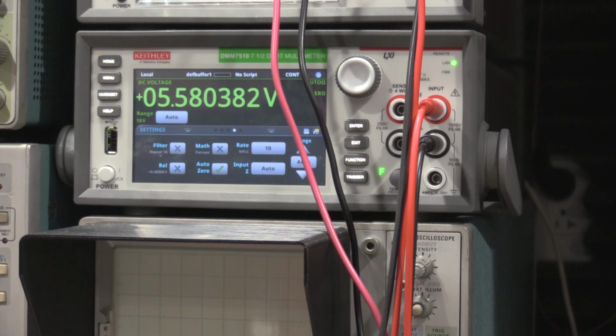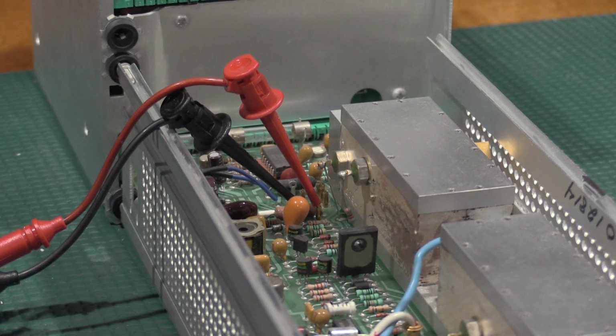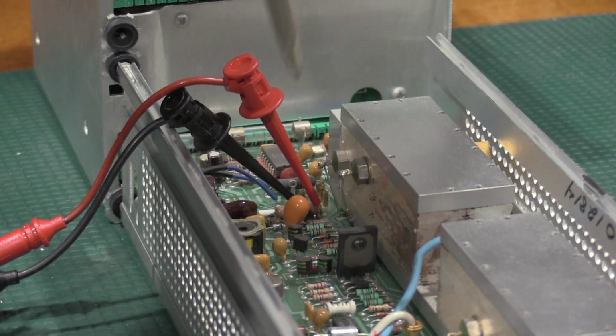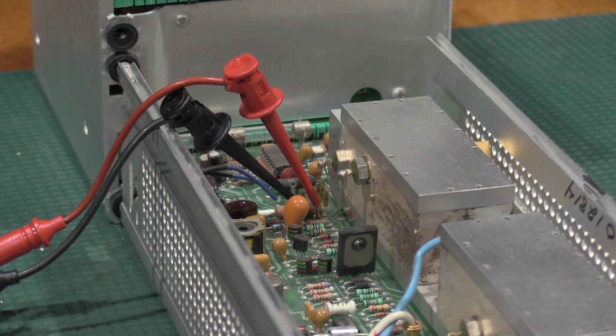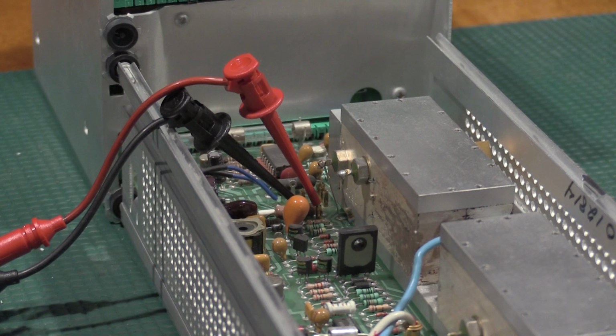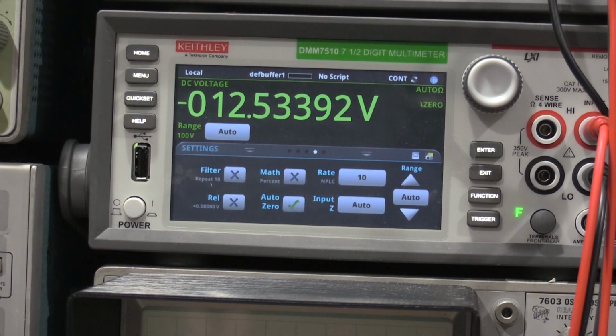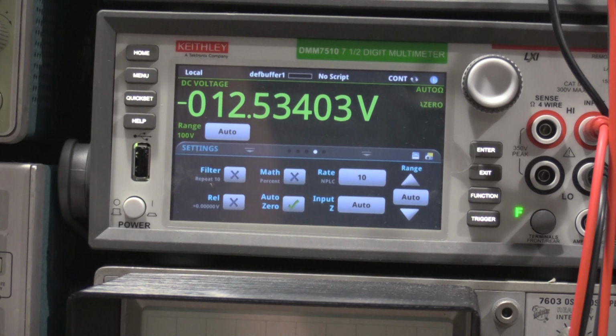Record a value that is 0.4 lower than the actual reading. Record this value, we use it in step 6, part 8. All right, so 5.58 minus 0.4, which would be 5.18. Okay, test E is the test point right up here with the ground, and I'm looking for negative 12 to negative 12.9 volts on the meter. We have negative 12.5, so our buffer bias voltage is perfect and right in the middle. So next we need to check the output of the 0.05 megahertz and the 6 megahertz references.